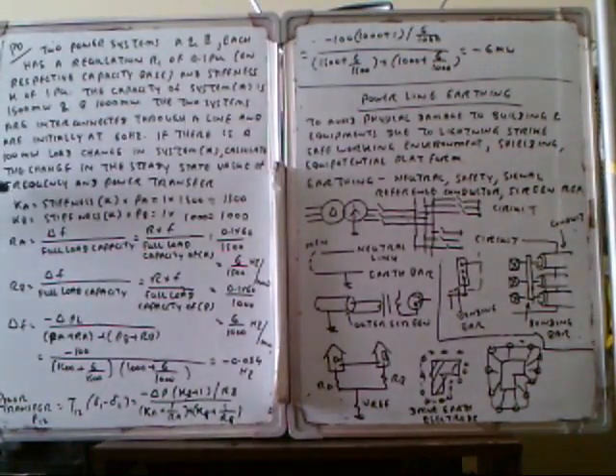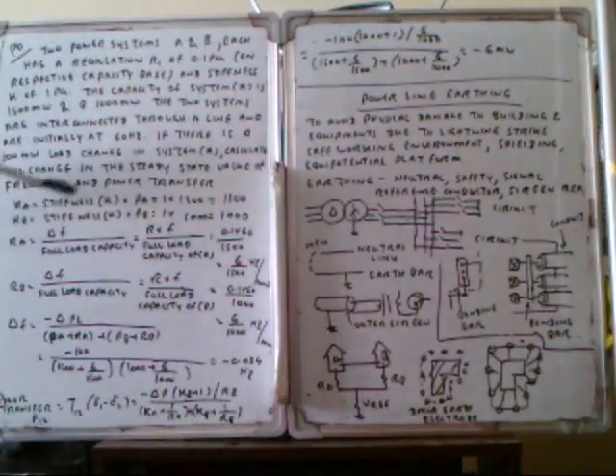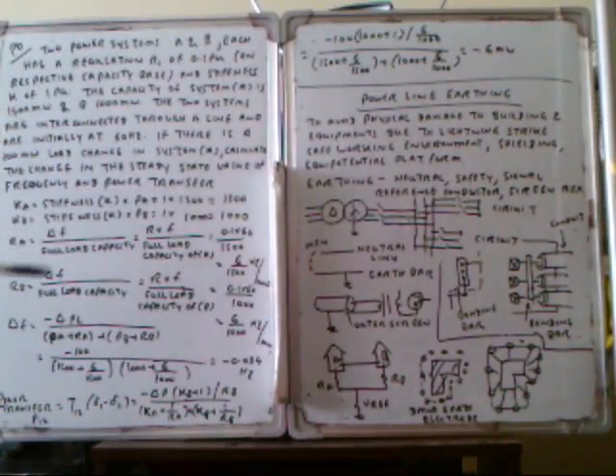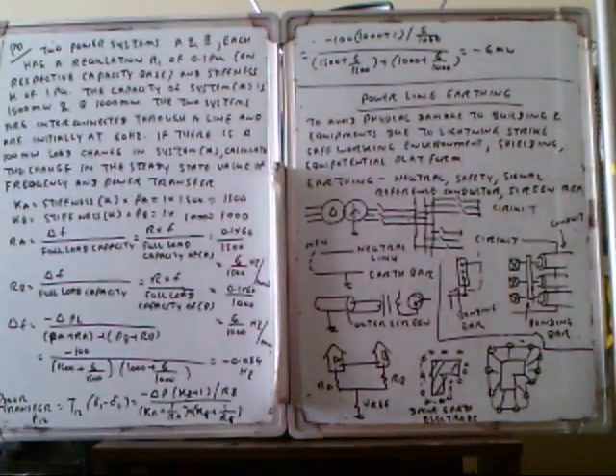First, we have to calculate K_A. K is the stiffness K multiplied by P_A. So the stiffness is already given here, 1 per unit, and the power P_A is 1500 MW, so you get 1500 MW.